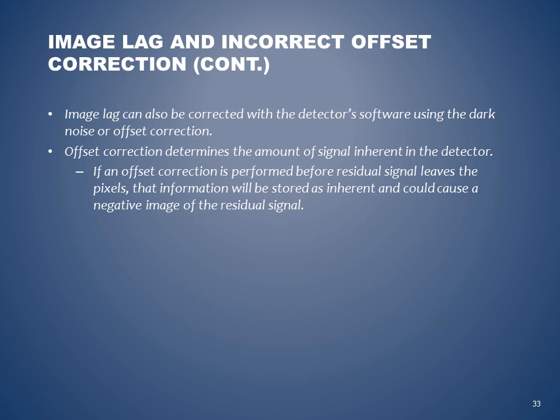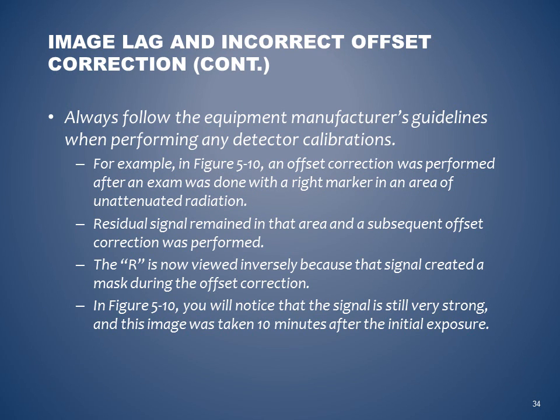Image lag can also be corrected with the detector software using the dark noise or offset correction. Offset correction determines the amount of signal inherent in the detector. If an offset correction is performed before residual signal leaves the pixels, the information will be stored as inherent and could cause a negative image of the residual signal. Always follow the equipment manufacturer's guidelines when performing any detector calibrations.